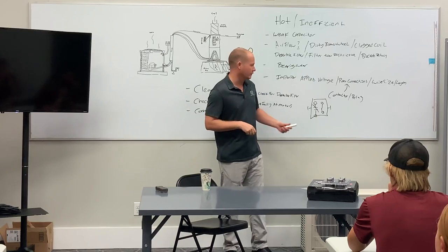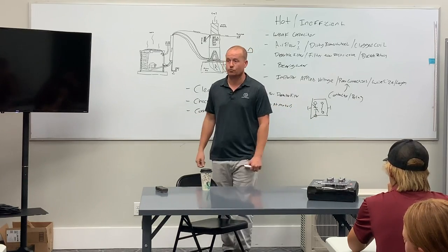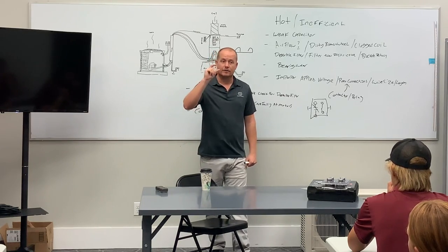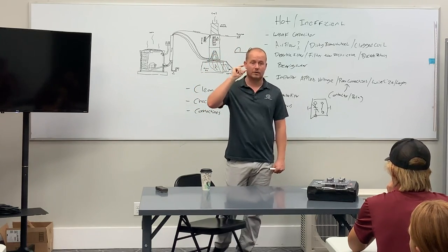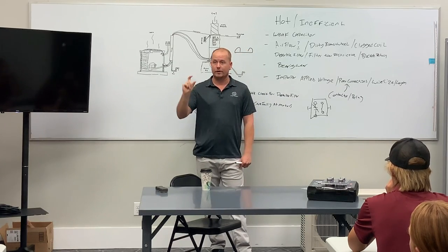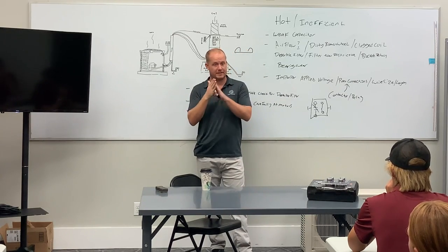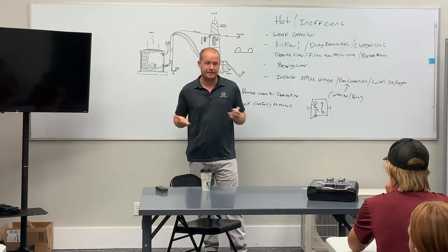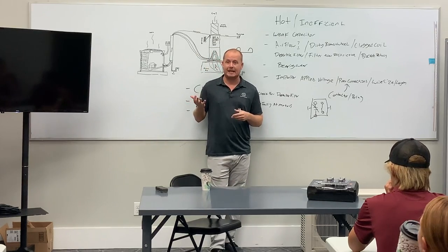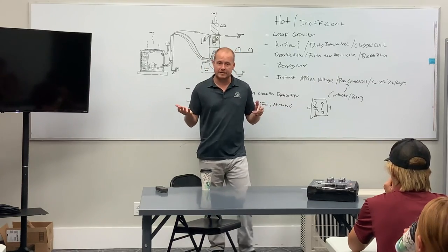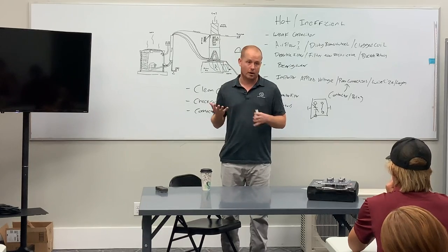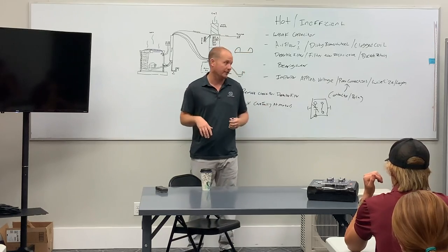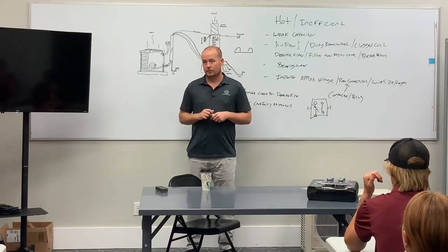But any amount of resistance in this contact point causes what within the contact point? Heat. Heat shows up in places where there is resistance. So when you have a poor connection and there's resistance between those wires, the carbons build up, you get heat there. And we don't want heat there for a couple reasons. One is that heat is wasted energy. But the other reason is that heat is going to continue to grow as that connection gets worse and worse and more resistance builds up, until the wire nut melts off, the contactor completely fails, whatever the case may be.